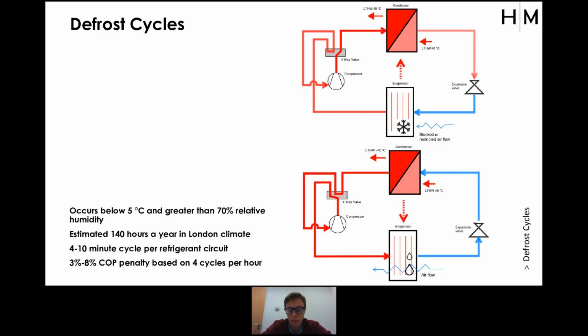For air source heat pumps only, this doesn't occur for water-to-water connected to other devices, but for air source heat pumps, you need to look at when the relative humidity is higher than 70%, when the temperature is below 5, and that will give you a time when you're going to have an energy penalty where the circuits go into a different mode, requiring to heat up the evaporator, which is the element that the air is basically an air heat exchanger, exchanging energy to the refrigerant circuit, and that will block up or be restricted in airflow, so reducing the output of your system.